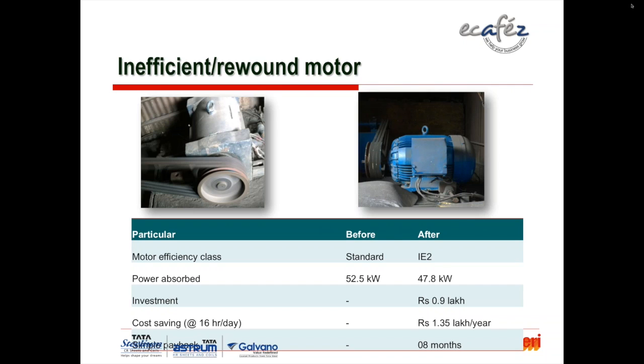The investment in the motor was about 90,000, and the cost saving was more than 1 lakh 35,000 rupees per year. So the payback was immediate. In fact, after we recommended it, they installed this motor pretty immediately.